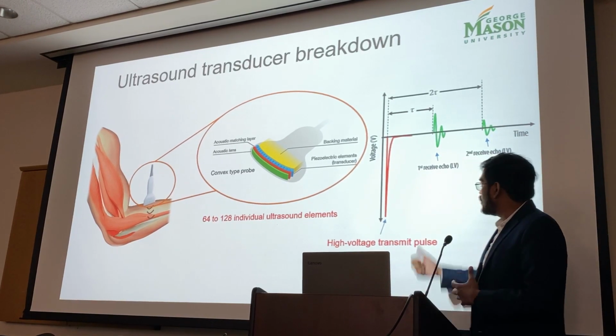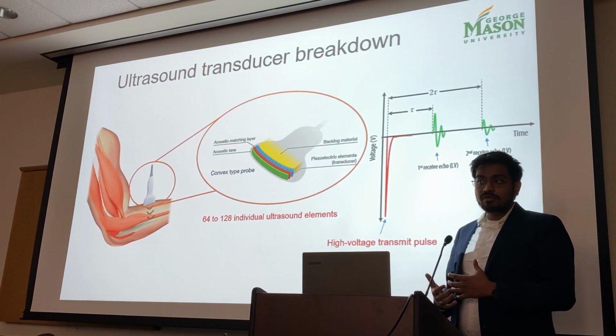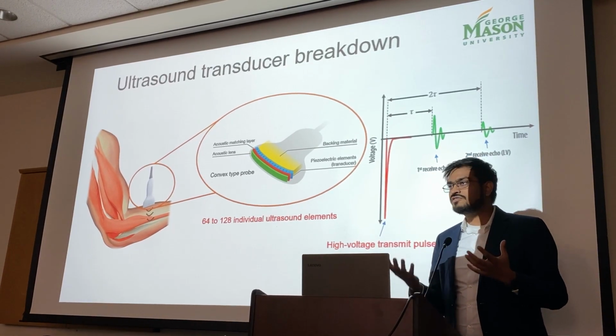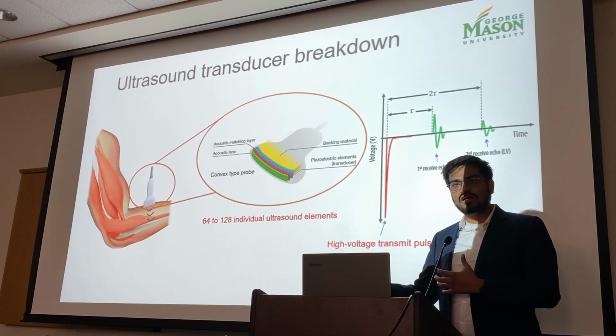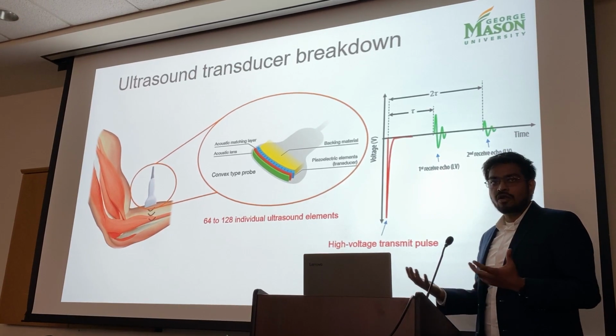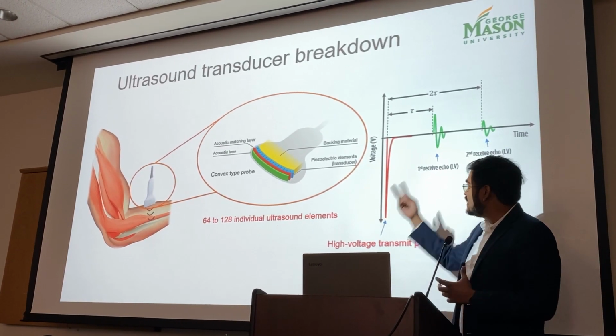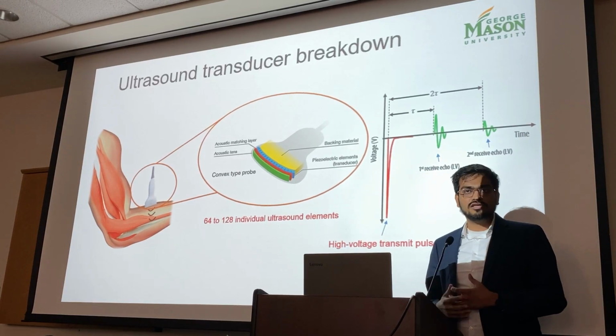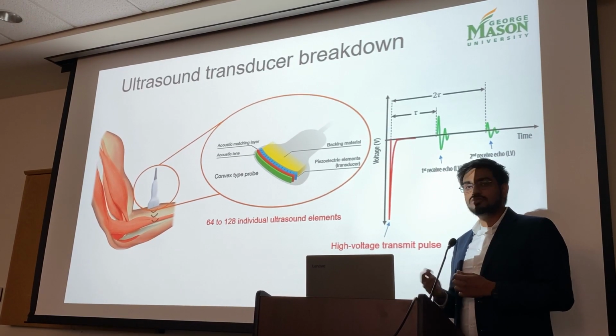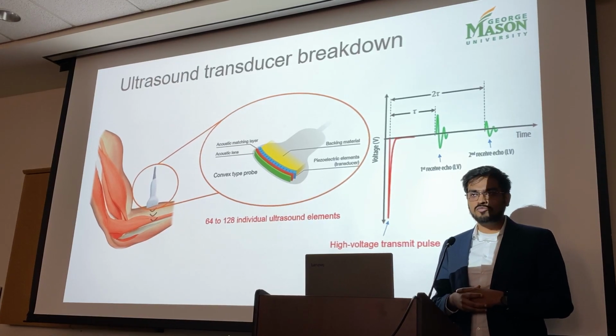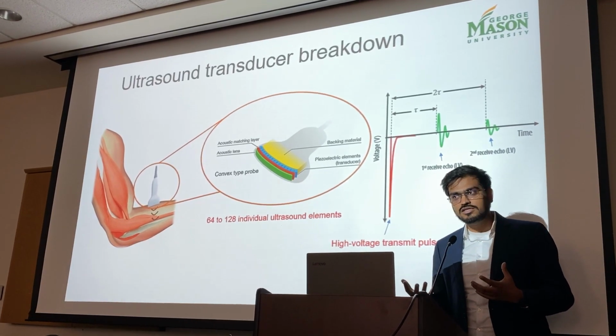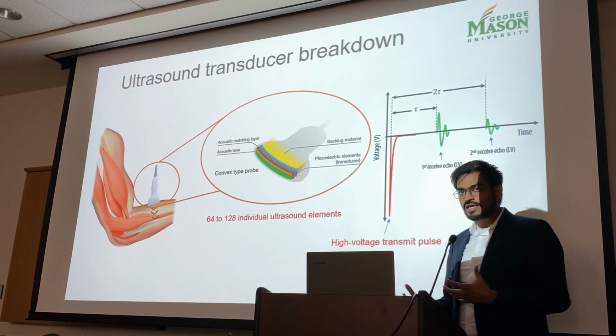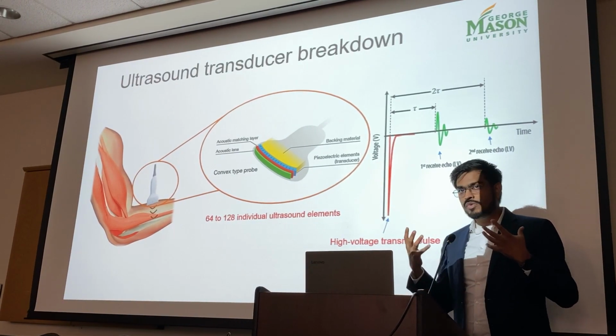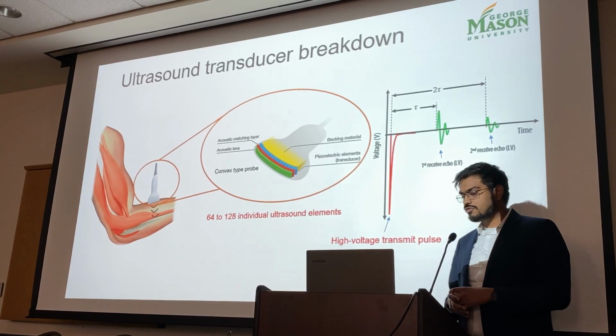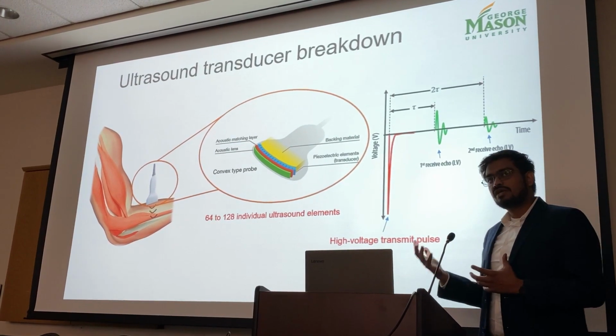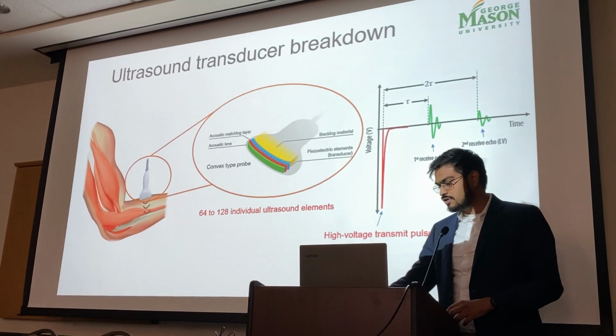that object is. So the measurement of time, when it's in the body, is in the order of centimeters, and at the speed that sound travels, around 1540 meters per second, these time periods are in the order of microseconds. So you're measuring very precise amounts of time, and it's very difficult to measure time that precisely. You need very high speed digitizers, which increases the cost, complexity, power consumption, and the form factor of clinical ultrasound systems. So these challenges make it really difficult to actually miniaturize ultrasound systems.